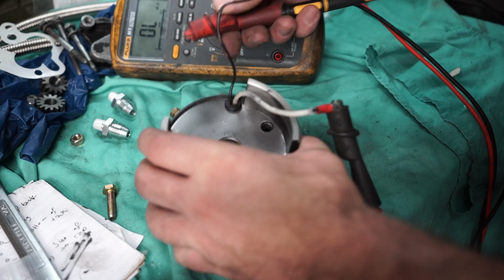There you go, you see the meter on the camera now. We'll clip one side of it to the white wire, and we'll clip the other side, take the nut off, clip it to the B terminal. 300 kilo ohms. That's ridiculous, should be like 1 ohm or less. We went to the L terminal just to make sure it's not shorted to that - it's not, a ton of resistance there. And the L terminal goes to that black wire, 1.5 ohms, which is about what we should expect.